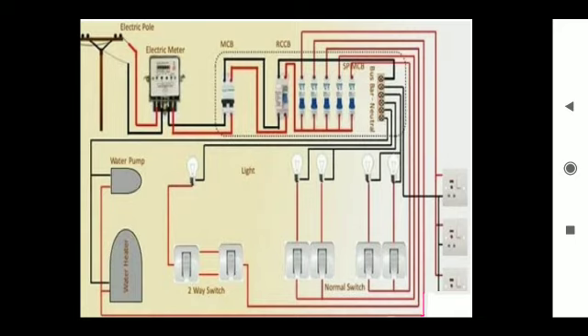The phase and neutral come from the service main and are connected to the incoming part of the energy meter, and the outgoing part of the energy meter is connected to the MCB and the RCCB. The MCB is used to protect the circuit from short circuit and overload current, and the RCCB is used to protect the human beings who are operating the electrical circuit from leakage current, and hence it is connected to the bus bar.